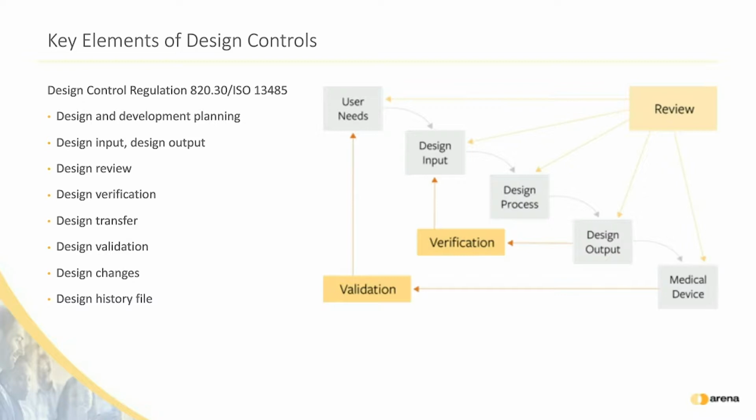The process usually involves fixing a bill of material that's stored in a spreadsheet, removing columns, maybe reformatting numbers, exporting a CSV, then uploading it into the ERP system. Next, manufacturing builds the medical device using design output, and that would be the bill of material, drawings, assembly instructions. The next step then is validation to make sure that the product as built will function to meet the user needs. All these tests and results must be documented. Validation is the most commonly referenced subpart of the Design Controls 483s.